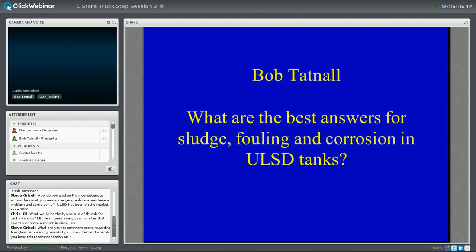But with heating oil systems, we used to deal with this. We had situations where 2 homeowners lived almost next door to each other, had similar age and type of heating systems. Tanks were put in the same time when the area was built up, and they both got their oil from the same oil company, which meant they both got deliveries from the same truck on the same day. And one of them was having big time sludge problems and the other wasn't. Why? Well, part of it might be the luck of the draw. Maybe one of them got a slug of contamination with their load and the other one didn't. Maybe one has a lot of sludge in their tank, but for some reason it just hasn't made itself out of the tank yet. It's hard to say. I don't know. That's a good question, and I wish I had a better answer.